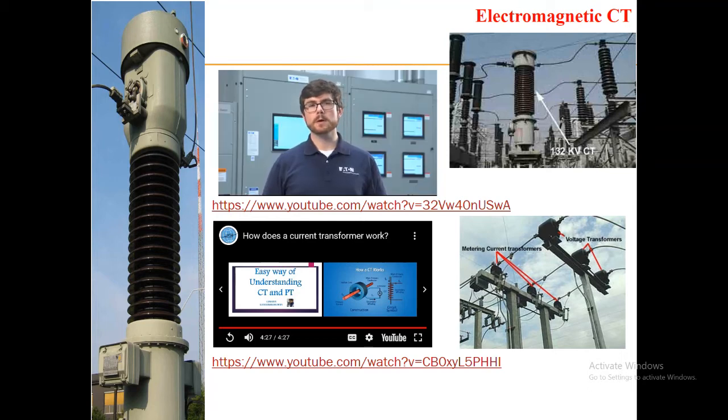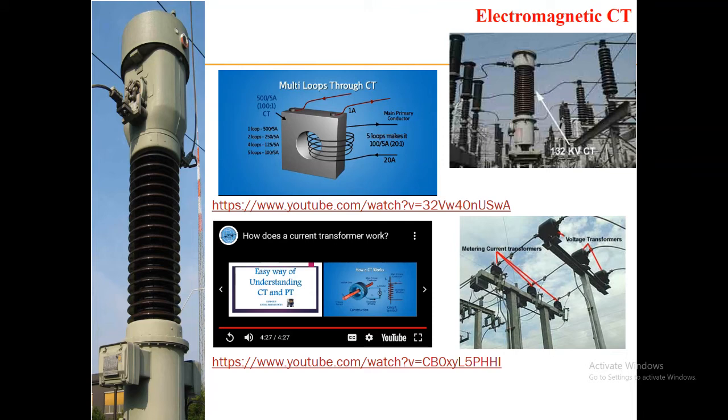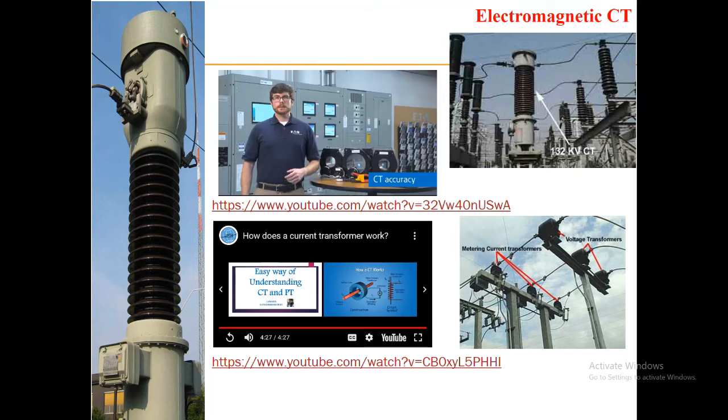All CTs output a current that is then used for metering, but temporary CTs like those used in Fluke and other power quality instruments add a terminating resistor on the secondary winding so that they output a voltage and can be open circuited when connecting the meter. With this resistor, these CTs typically have a rating of 10 millivolts per amp or 100 millivolts per amp. The lower range ratio is usually used for secondary measurements, in other words clamping onto the 5 amp secondary of another CT.